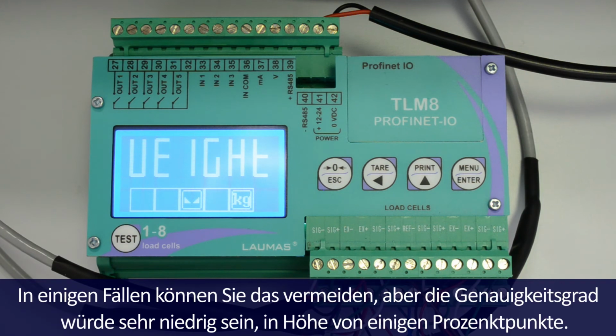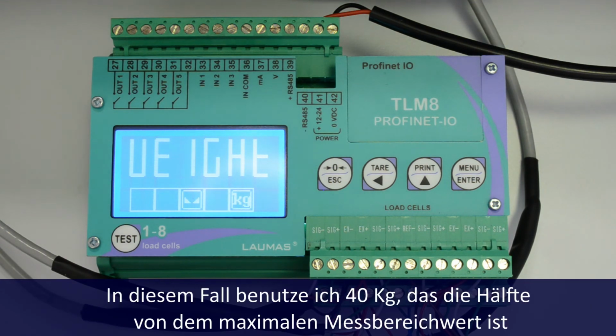The next important menu is weight. This is the weight correction menu. In some cases you could avoid it, but the accuracy you will get will be quite low, in the order of some percent. So you normally should do it. Put a known sample mass on the scale. The closer the value to the system's capacity, the better. In this case, I will use 40 kilograms, which is 1/2 of the system's capacity. 1/2 of the system capacity is the minimum weight we recommend for real calibration. Let's do it.